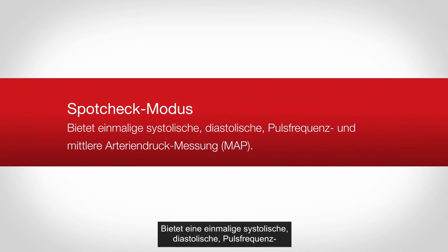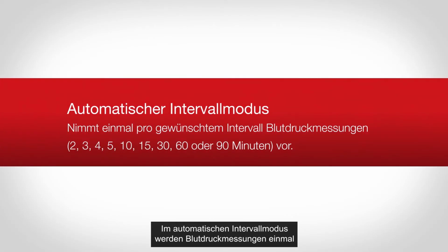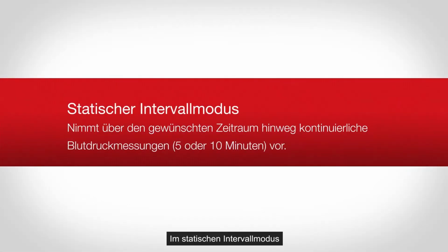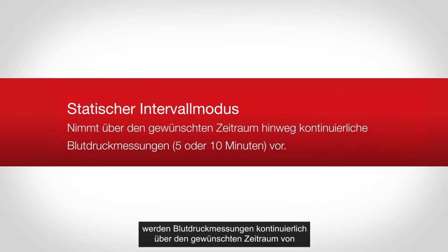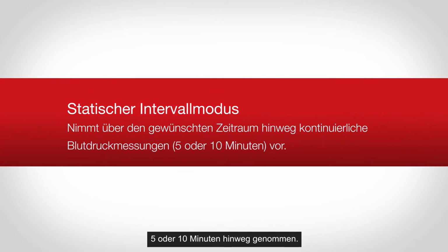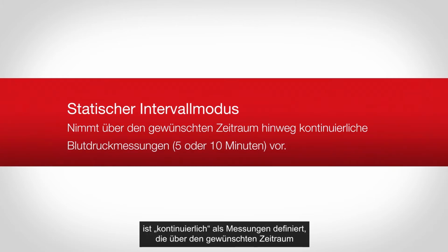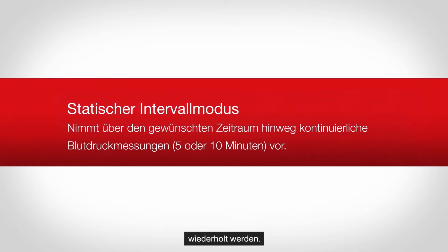The non-invasive blood pressure module has 3 distinct measurement modes: spot check, automatic interval, and stat interval. Spot check mode provides a one-time systolic, diastolic, pulse rate, and mean arterial pressure MAP measurement. Automatic interval mode will take blood pressure measurements once every desired interval. Intervals can be set between 2 minutes and 90 minutes. Stat interval mode will take blood pressure measurements continuously for the desired duration, 5 minutes or 10 minutes. In this mode, continuous is defined as measurements that are repeated one after another for the desired duration.